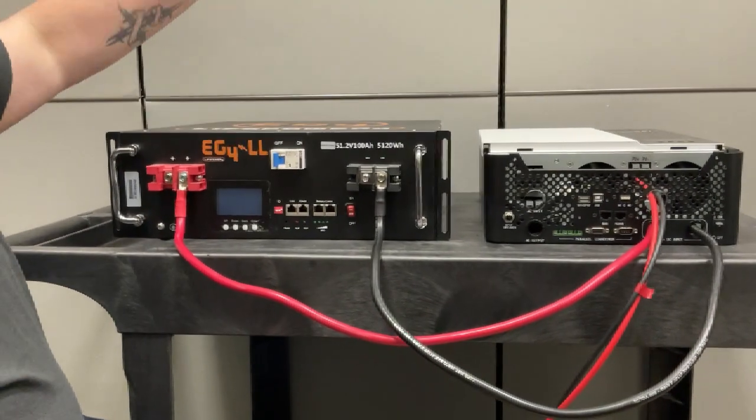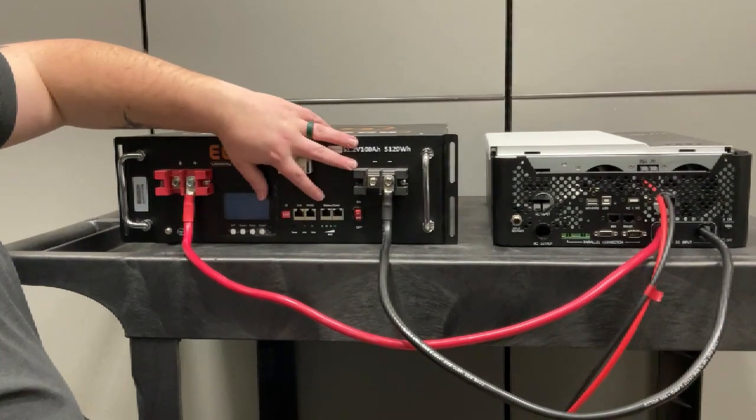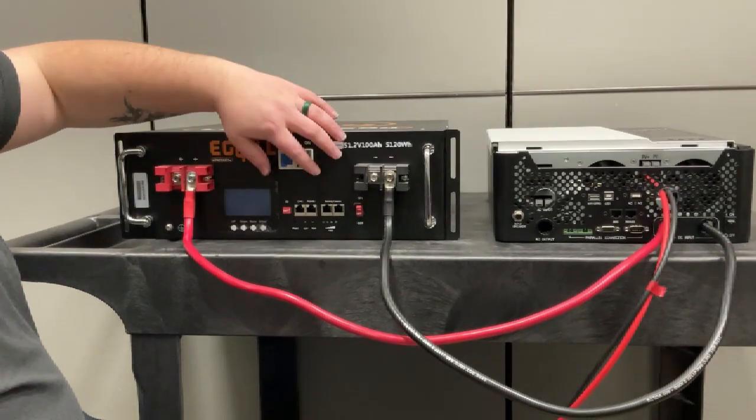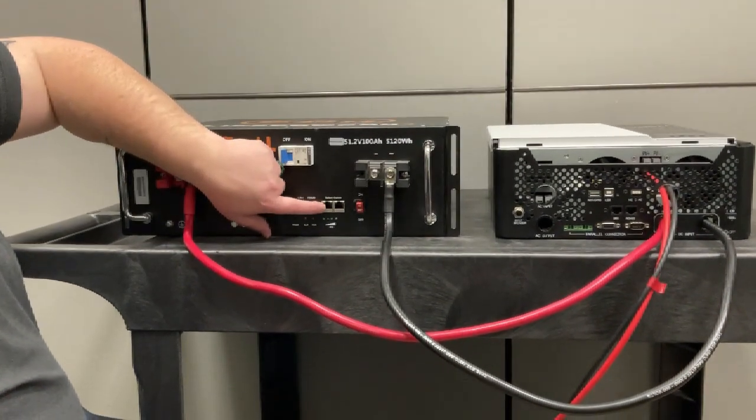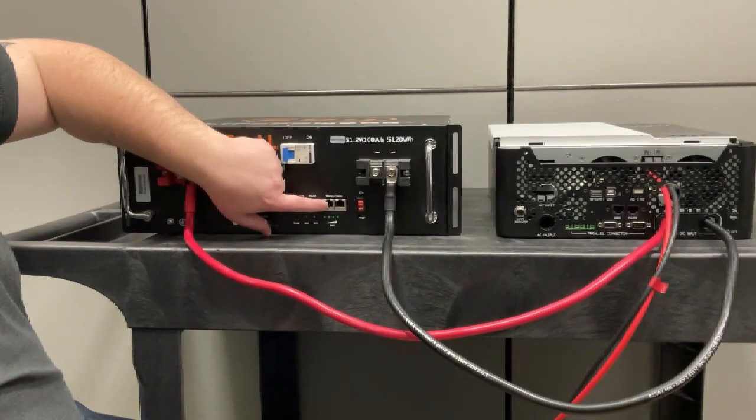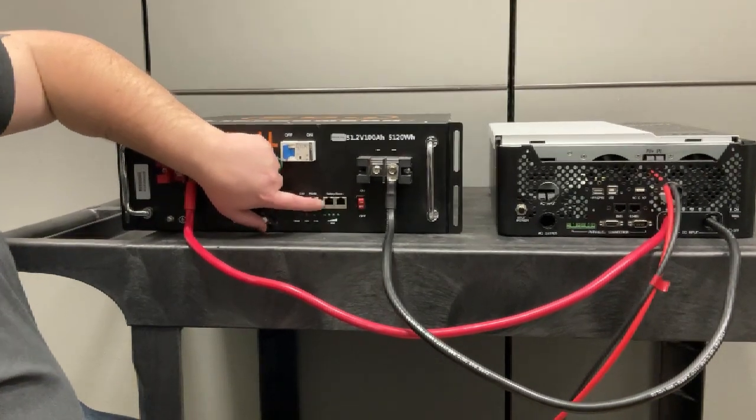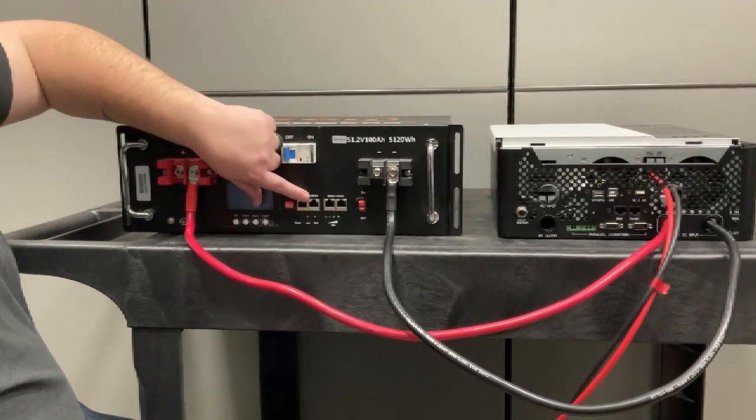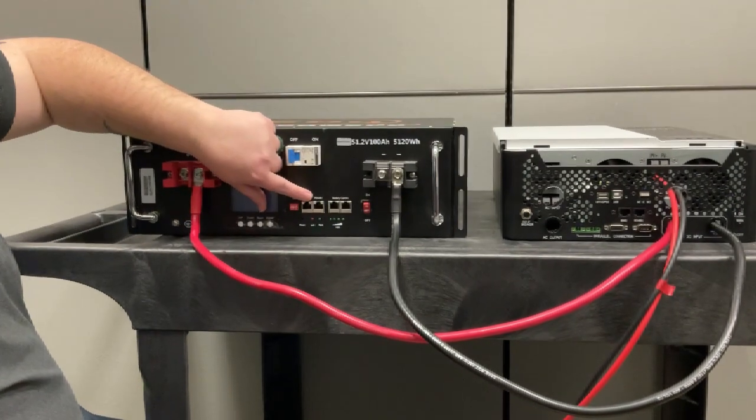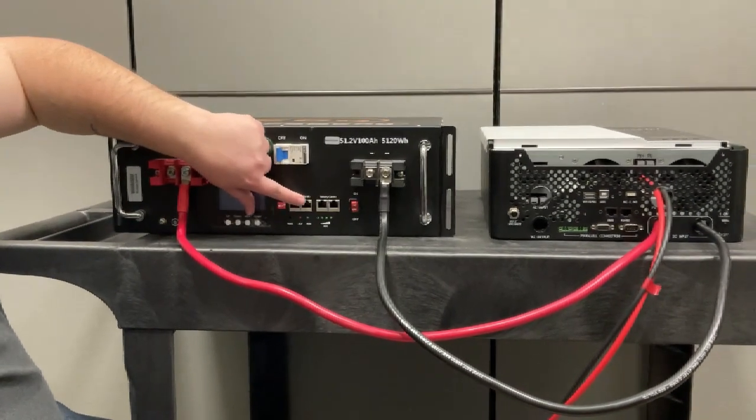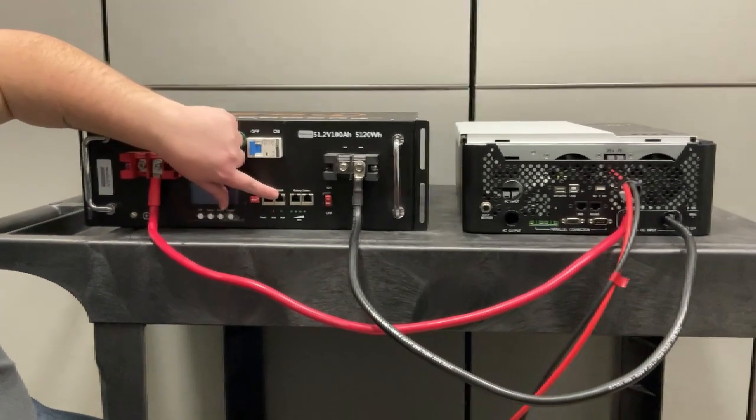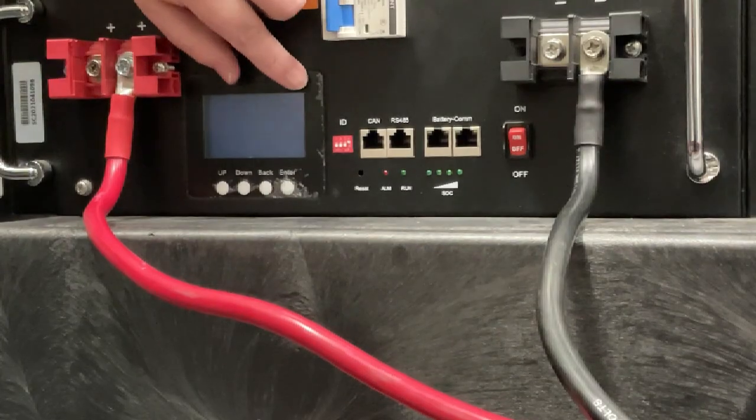So you've daisy chained them all the way up the stack and on your master battery, it should end with you having a cable coming into your battery port here from the battery below it. And then you'll have your cable going out of the RS-485 port here and into your inverter.